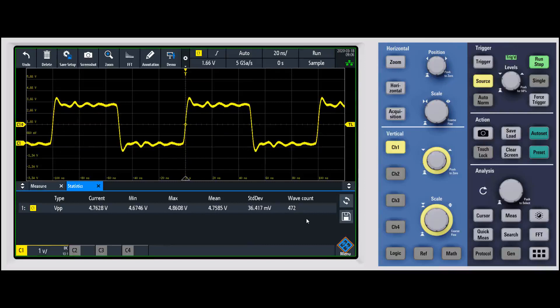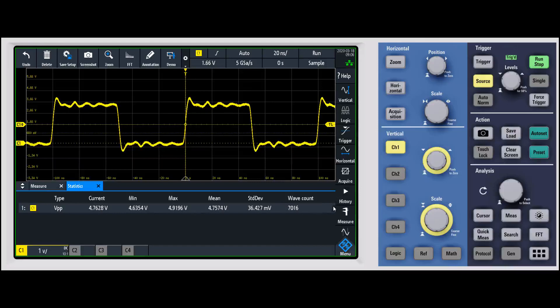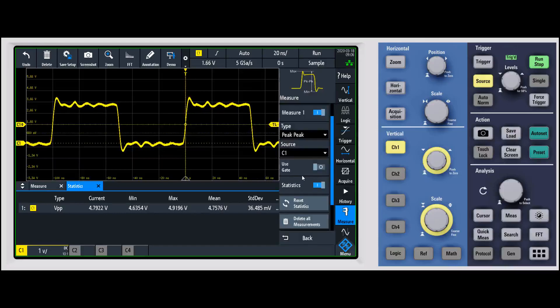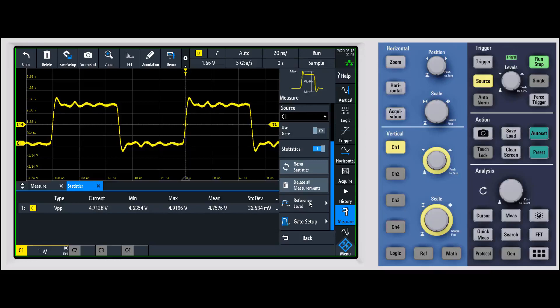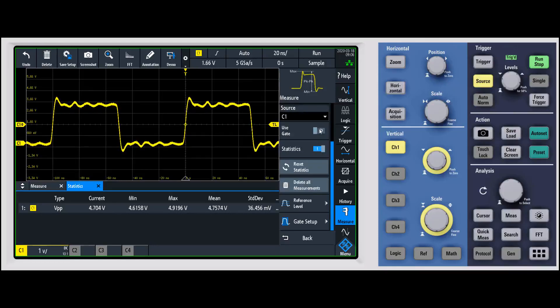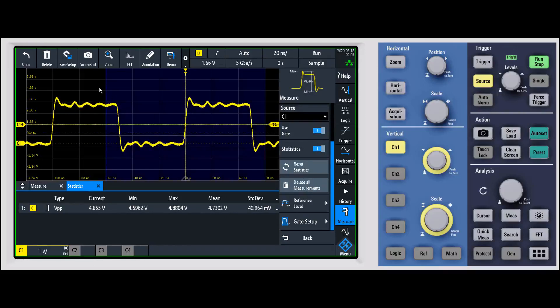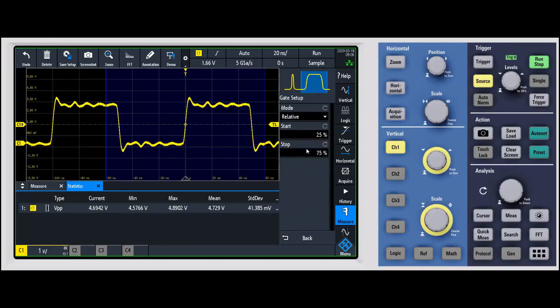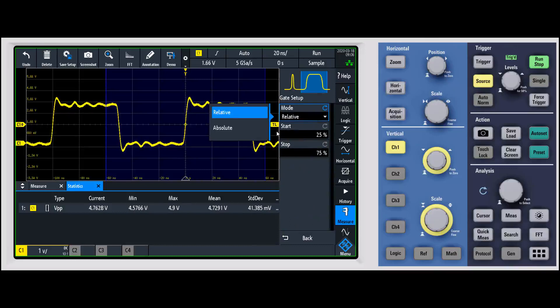If you want to reset the statistics, there's a button right here and it will start fresh. A couple of other things under the measurement menu worth knowing: one is the reference level. When making vertical measurements, you can set the different levels — we default to 10/90 but you can change that to whatever you see fit. Finally, you can use a gate to measure just a certain portion of the waveform. When you turn on the gate, you'll see a blue bar indicating the gated region, and you can define it in either percentage or absolute values.